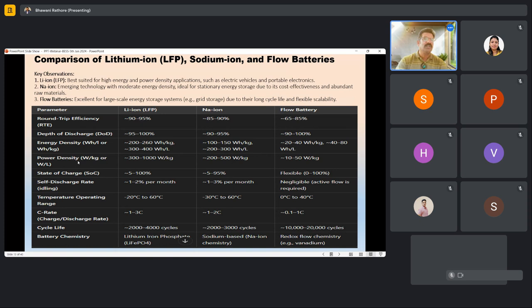Lower maintenance. Power density: LFP battery 300 to 1000 watt per kg. Power density means how much power it can deliver per kg. Sodium ion is 200 to 500 watt per kg, and flow battery is again very less. State of charge: 5 to 95% for sodium ion, where 5 is the minimum, and LFP is 100%, which is again good. Flow battery is flexible, 0 to 100%.